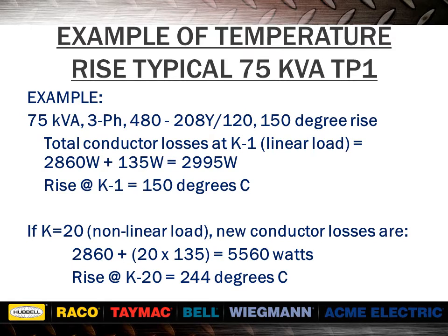In this example, a standard distribution 75 kVA transformer has 2,995 watts of total conductor losses at k-1, assuming a linear load. However, if the load is not linear — for example, at k-20 — the new losses would be 5,560 watts. This would increase the transformer temperature rise from 150 degrees Celsius to 244 degrees, resulting in overheating, shortened transformer lifespan, and possible cause for failure.